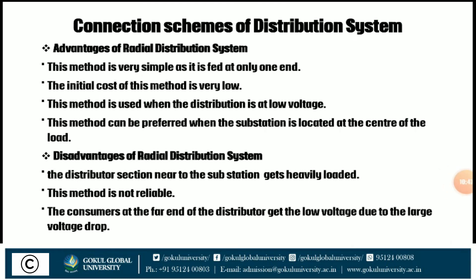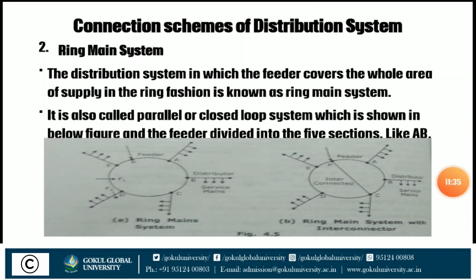Advantages of the radial distribution system: this method is very simple as it is fed at only one end; the initial cost is very low; it is used when distribution is at low voltage; and it can be preferred when the substation is located at the center of the load. Disadvantages: the distributor section near the substation gets heavily loaded; this method is not reliable; and consumers at the far end get low voltage due to large voltage drop.